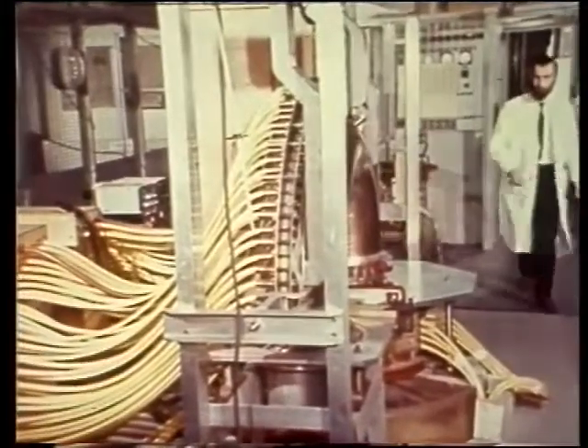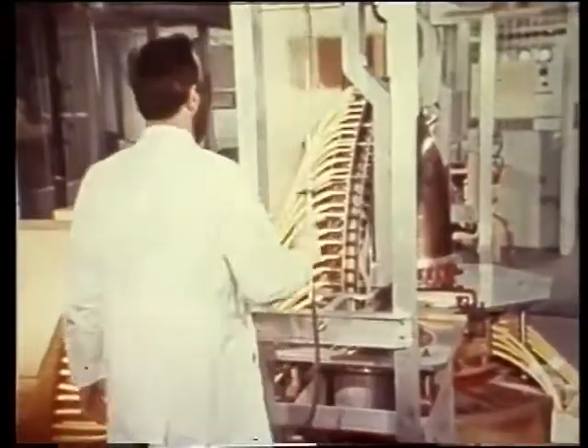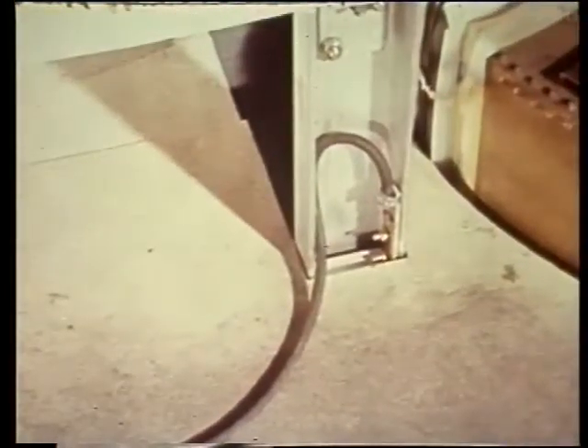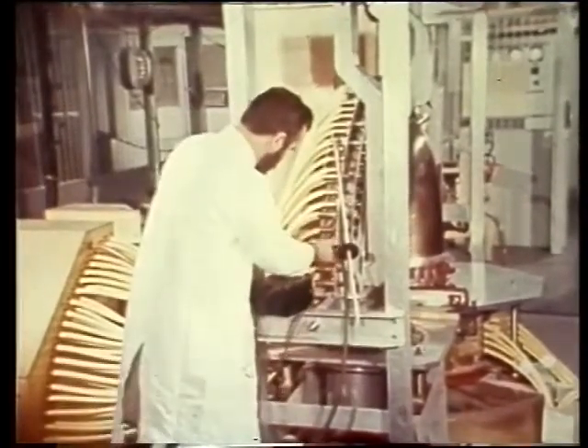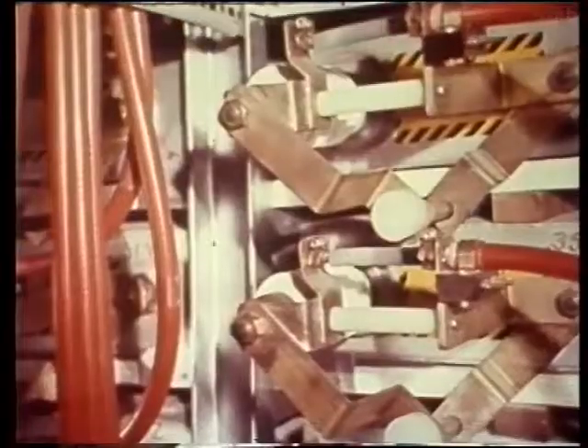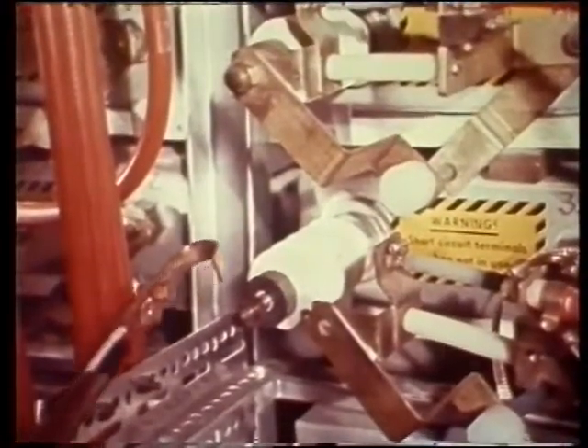But switches can go wrong and connections can fail. So as a final precaution, any HT circuit on which a man is going to work must be earthed with an earthing stick. An earthing stick isn't a magic wand — just touching a circuit doesn't make it safe. One must remember that capacitors sometimes recharge by leakage from other circuits or from their own dielectric energy. In only half an hour, they can build up sufficient charge to give a dangerous shock.